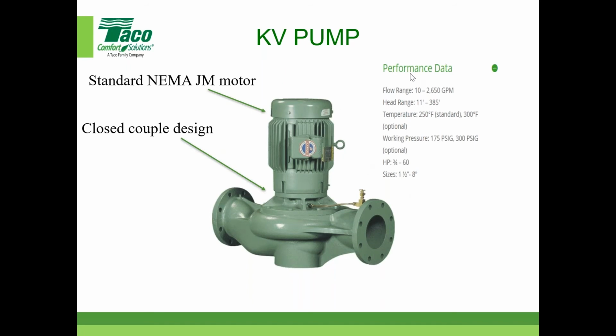As you can see here, the KV doesn't go up nearly as close in horsepower as the KS does, so just keep that in mind. But everything else is pretty much the same. Obviously the sizes and horsepowers are different, but this information is pretty much the same between the two. And again, I want to reemphasize: the same model, KV or KS, with the same numbers after it, in a given horsepower and impeller cut, will give you the same flow and head out of each one. So some basic stuff to understand there.